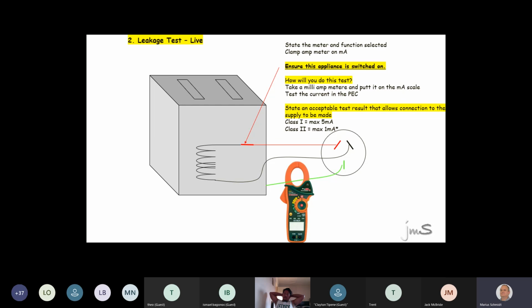Mouthful, eh? So what's the maximum current? 5 milliamps for class 1 appliances. For class 2, 1 milliamp. Cool. It's a real mouthful. There we are, 5 milliamps. Maximum 5. If it goes any bit more, mommy's going to get a bit of an afro.